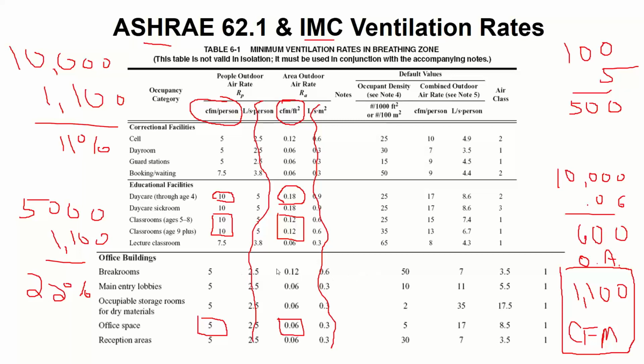Mike asks, who are you ventilating for when the building is unoccupied? Boilers and VOCs, but we're not ventilating the occupied spaces when unoccupied. However, if I have boilers, I still bring combustion air in for them, but that combustion air is a separate airflow path to the boiler room.